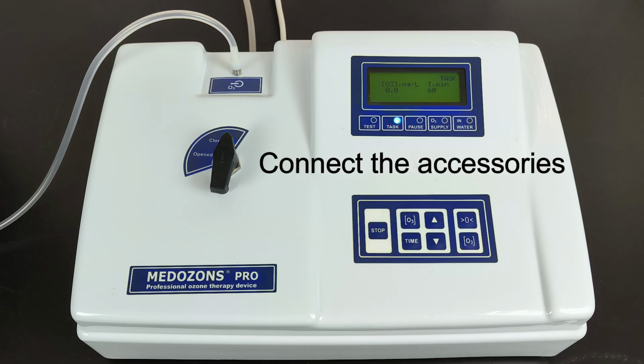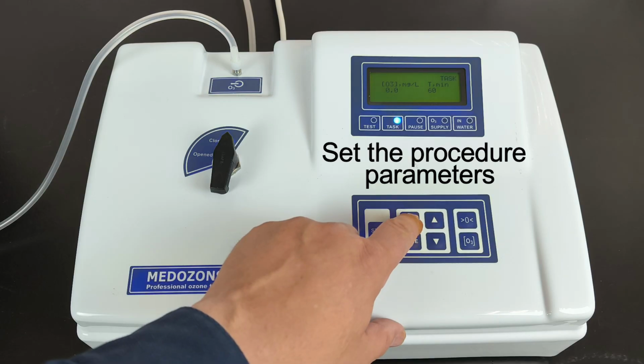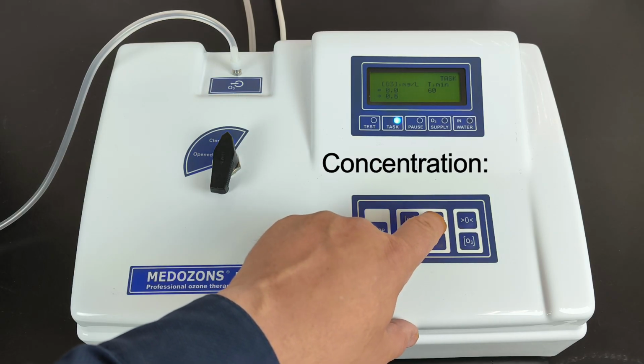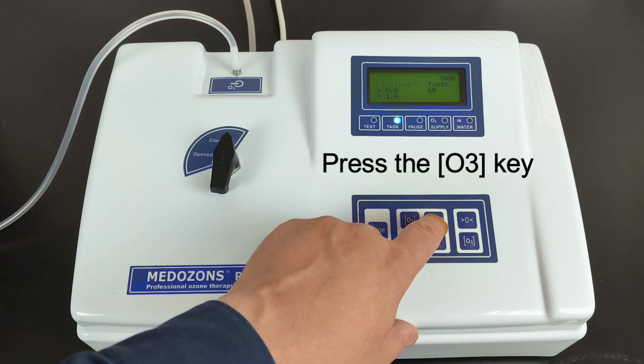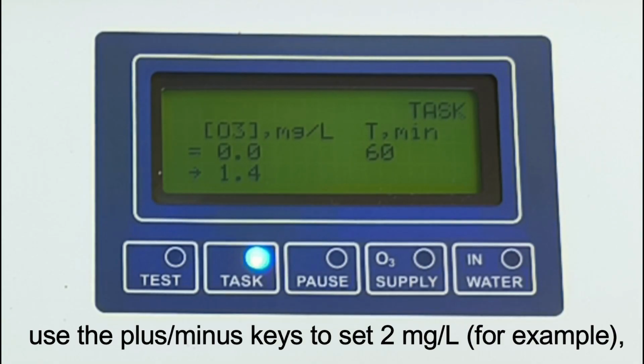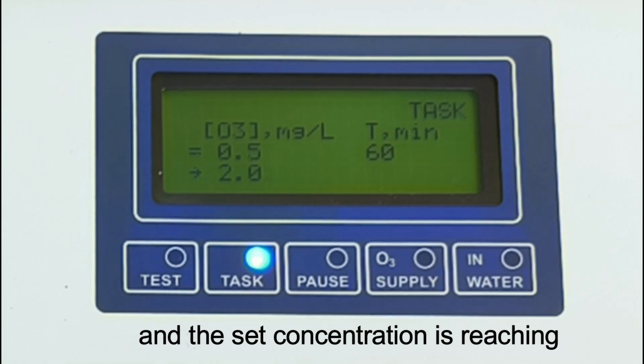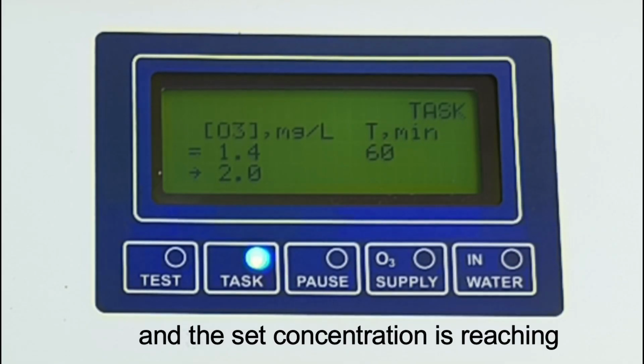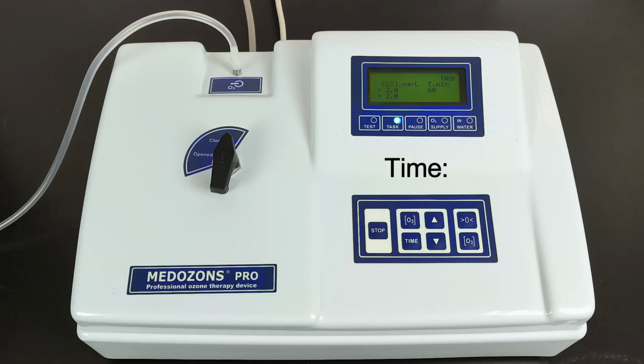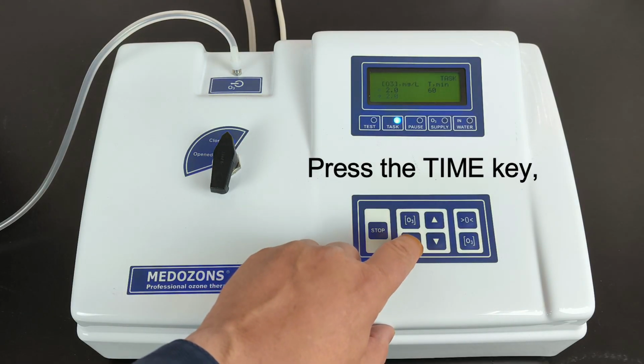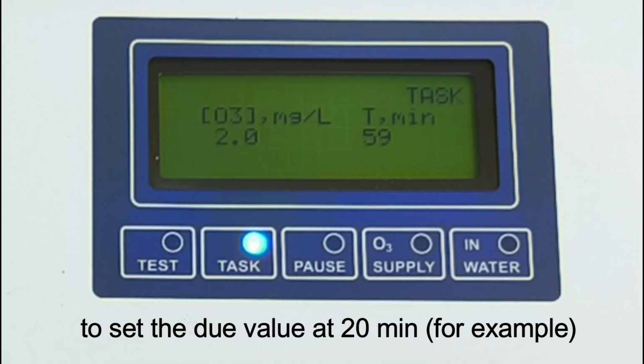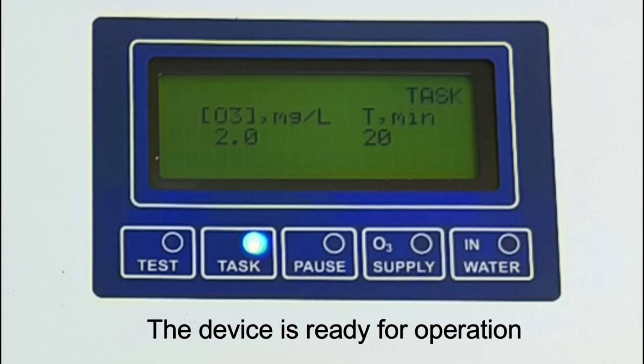Procedure. Connect the accessories. Set the procedure parameters. Concentration. Press the concentration key. Use the plus-minus keys to set 2 mg per liter, for example, and the set concentration is reached. Time. Press the time key. Use the plus-minus keys to set the time value at 20 minutes. The device is ready for operation.